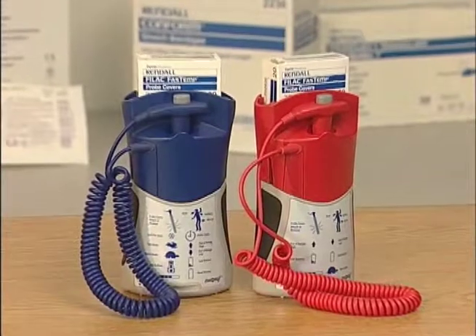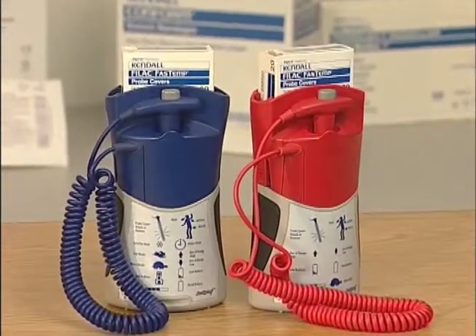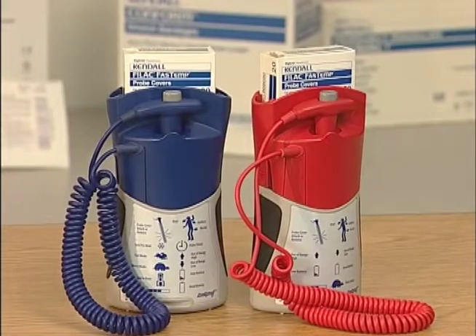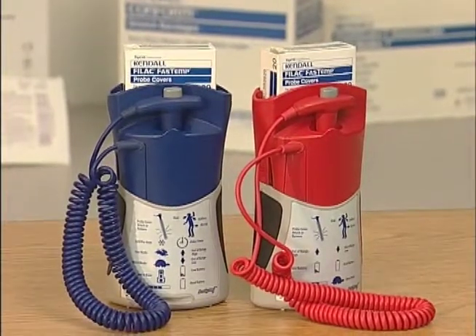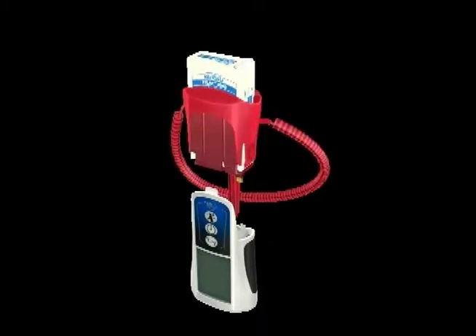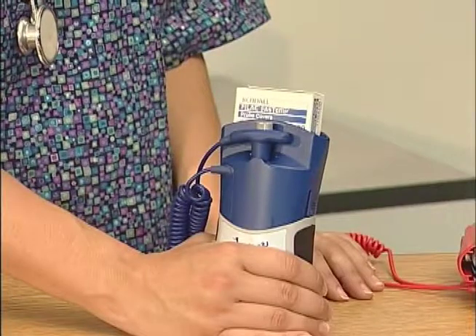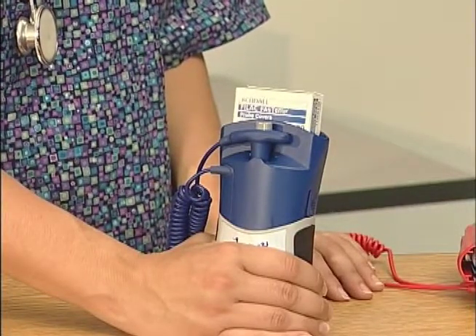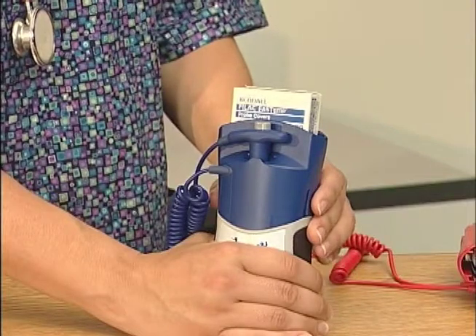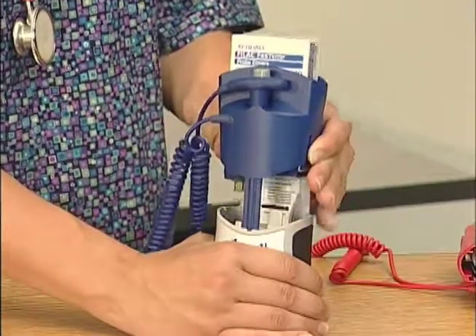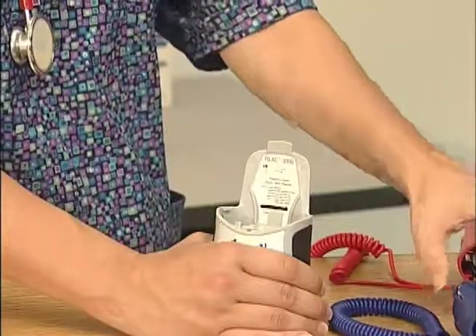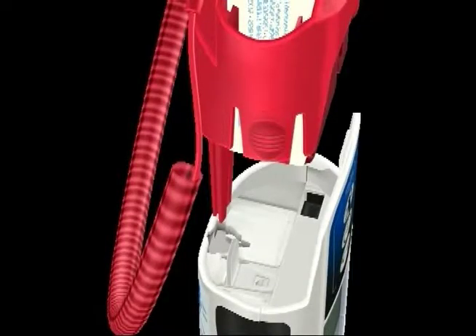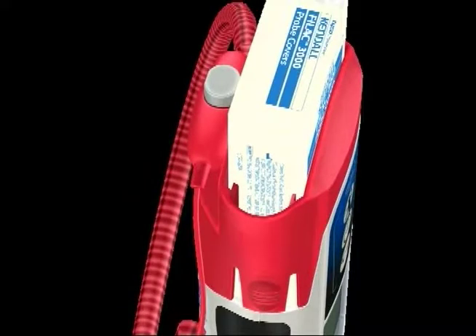To help reduce the chance of cross-contamination, the Filac Advanced Thermometer utilizes separate chambers for oral, axillary, and rectal temperatures. The blue chamber and probe are used for oral and axillary temperatures, while the red chamber is used for rectal temperatures only. To remove an isolation chamber and probe assembly, grasp the isolation chamber from each side, squeeze inward, releasing the snaps, and slide the isolation chamber up to remove. To install an isolation chamber, align the probe well finger with the opening in the top of the unit, and slide the isolation chamber down until the side snaps click into place. The probe is connected to the thermometer automatically.